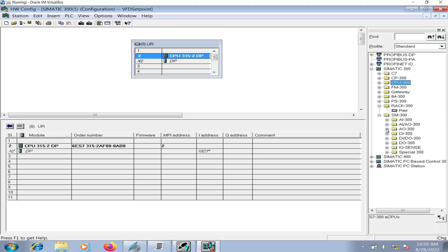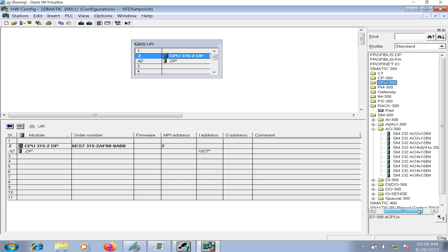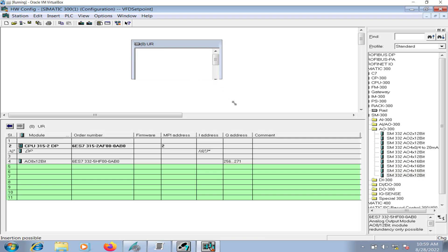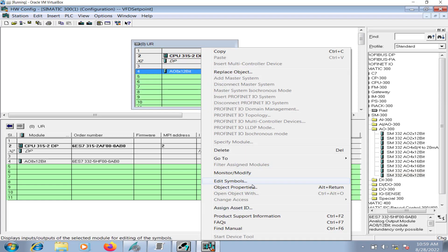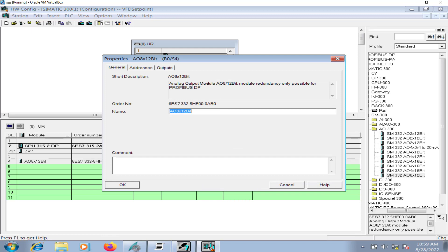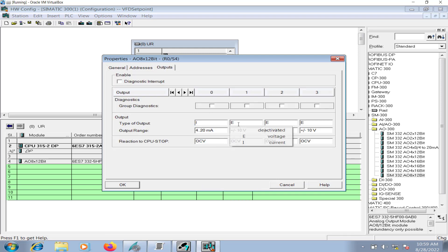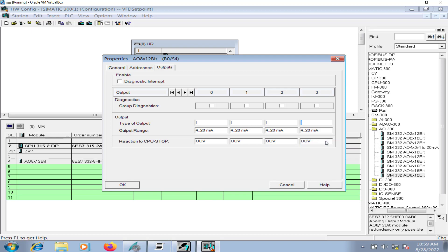Bring in a Siemens S7-300 rack to the hardware configuration, add the CPU 315-2DP, and I will insert an analog output card of eight channels, each 12-bit configuration. Go to the object properties outputs.